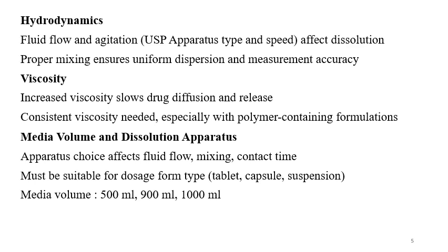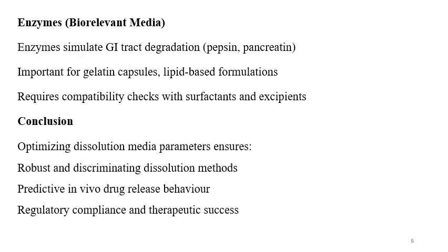Apparatus choice depends on fluid flow, mixing and contact time. It must be suitable for the formulation type like tablet, capsule or suspension. Media volume typically 500 ml, 900 ml or 1000 ml is considered for dissolution testing.